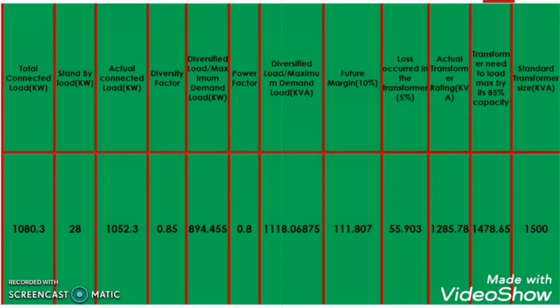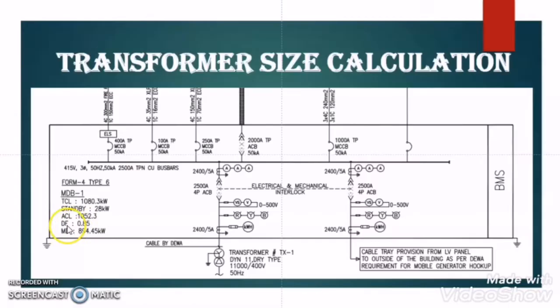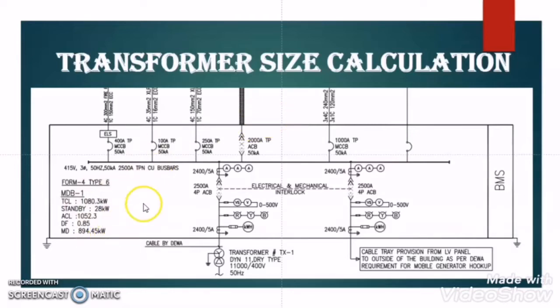I tabulated this here. The total connected load in kW is 1080.3 kW, standby load is 28 kW, and the actual connected load is total connected load minus standby load, that is 1052.3 kW. The diversity factor is given as 0.85 — the overall diversity factor of the loads connected with this MDB is 0.85. You will understand this video more conceptually if you already watched the previous part 1 video on transformer sizing.